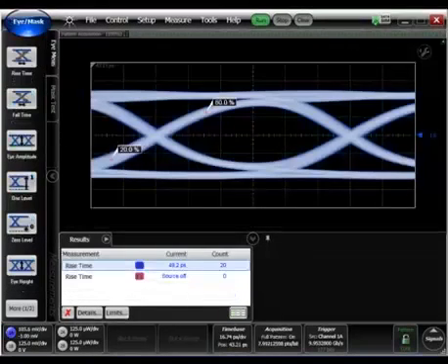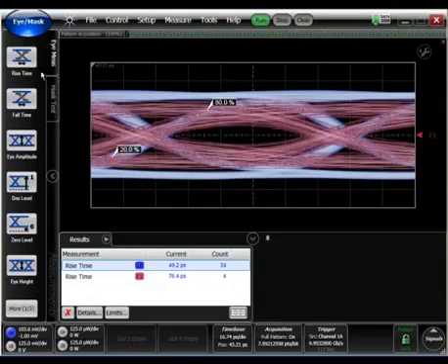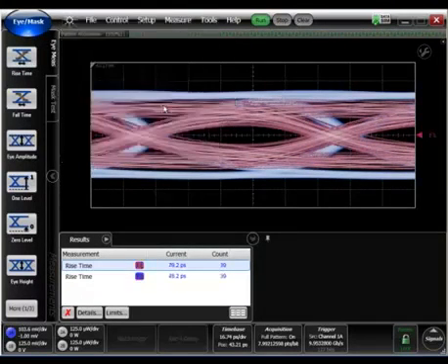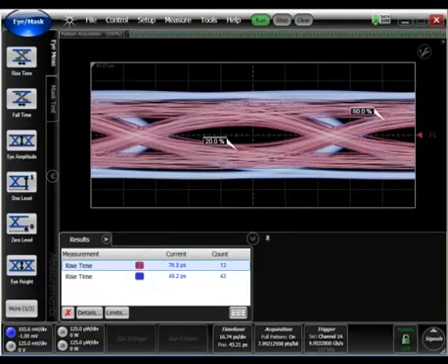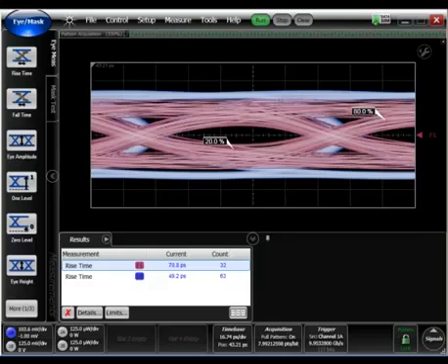Another powerful feature of the FlexDCA is waveform signal processing. Using the built-in circuit modeling features, you can observe how the chipset performs in the customer's environment. Here we see two eye diagrams that are played back — one is the original waveform, and the other shows the effect of the customer's modeled circuit environment.